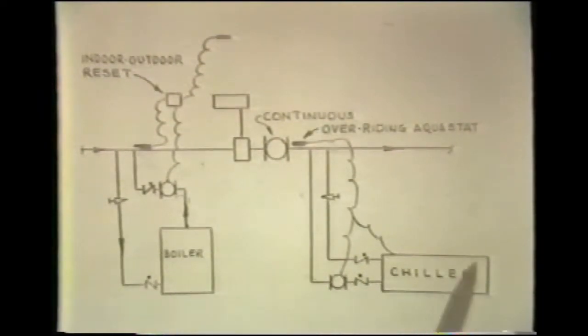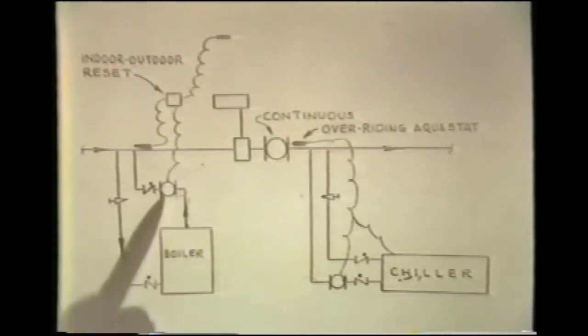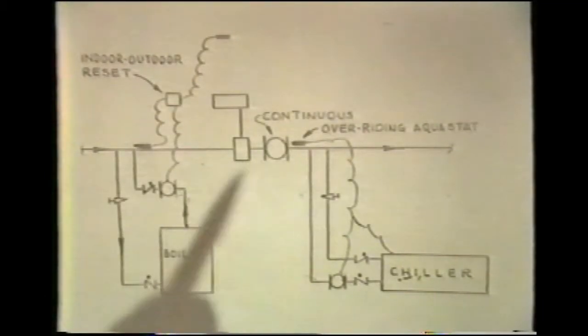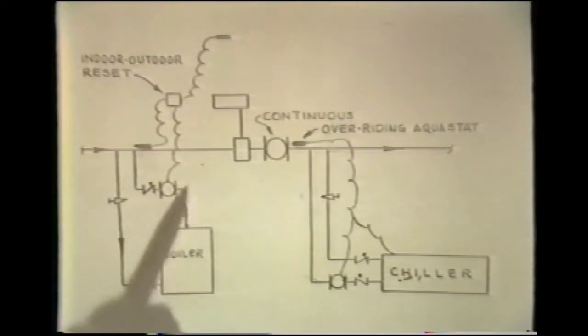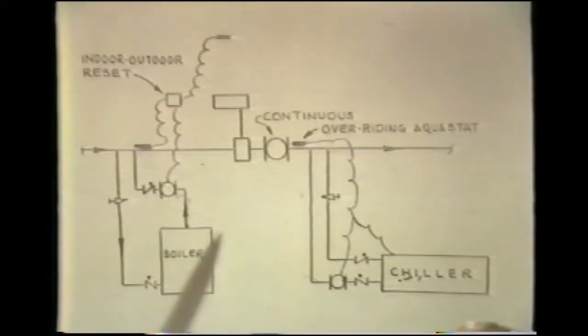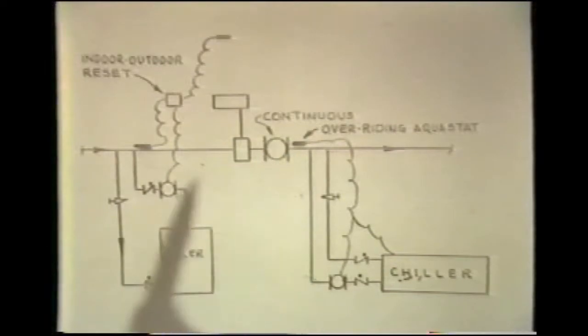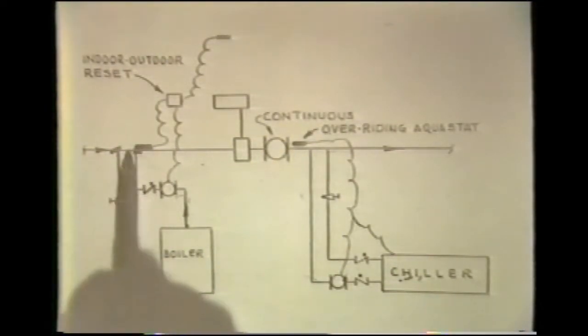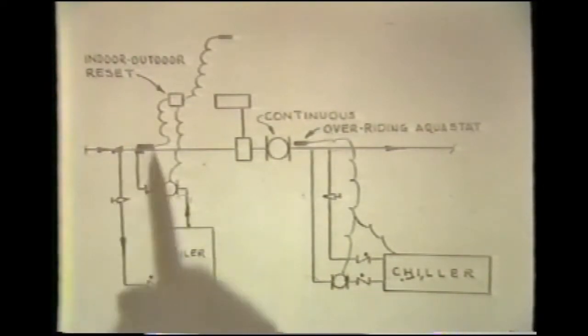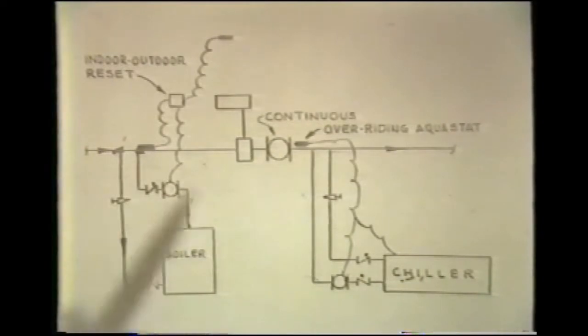temperature. During the summertime, we operated the chiller and its pump. During the wintertime, the chiller and its pump were shut off. The boiler injection pump then provided the necessary reset temperature for the secondary circuit. Let's continue now, and again, there are many applications for injection pumps that have been used and applied simply based on the very simple conceptual idea that if in primary secondary pumping we provide the necessary common piping, which has a low pressure drop, we can completely disassociate the pumping of a primary loop from the secondary loops.